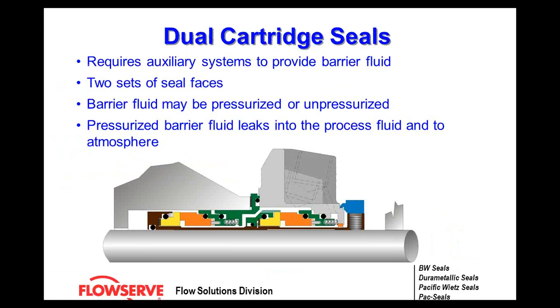This is another variation of a cartridge design in a dual orientation. Dual seals require an auxiliary system, so you must have barrier fluid in and out — it's simply two mechanical seals, one inside and one outside.